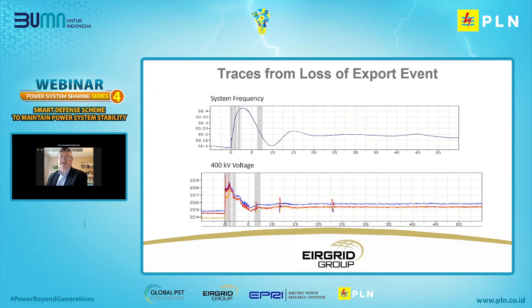So this is a real example of loss of export on an interconnector. At time 0 there, you can see that system frequency is shooting up to 50.4 hertz, and obviously we're activating the tripping of wind farms and the run back, so the rise is arrested there at about 50.4 hertz and brought back down within 10 seconds to 50.1 hertz. Then operators take over with manual interventions. Okay, next slide.